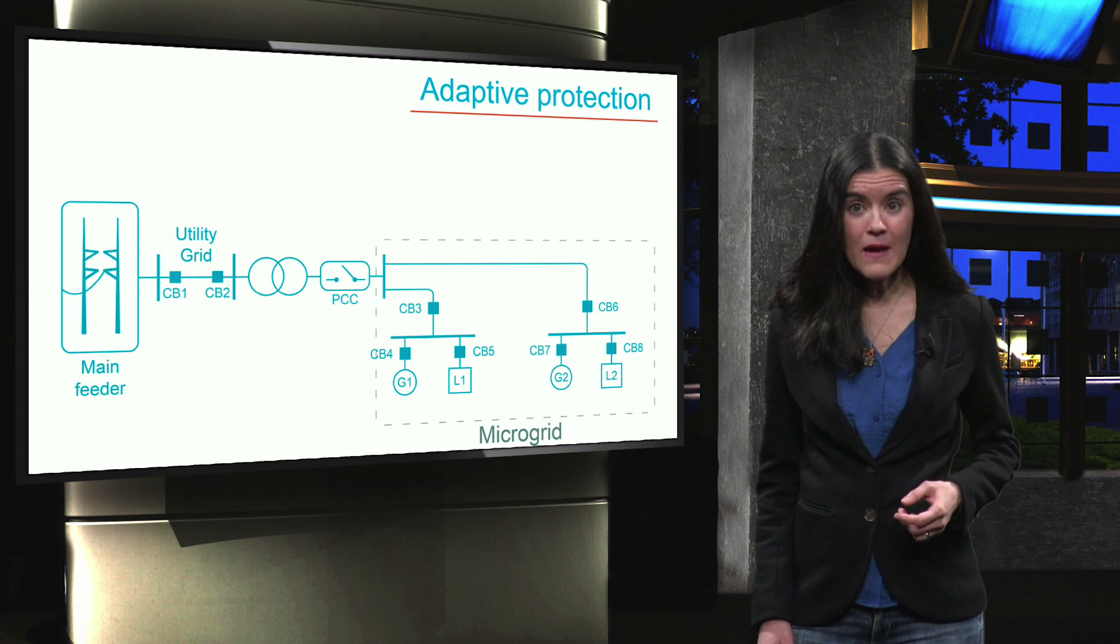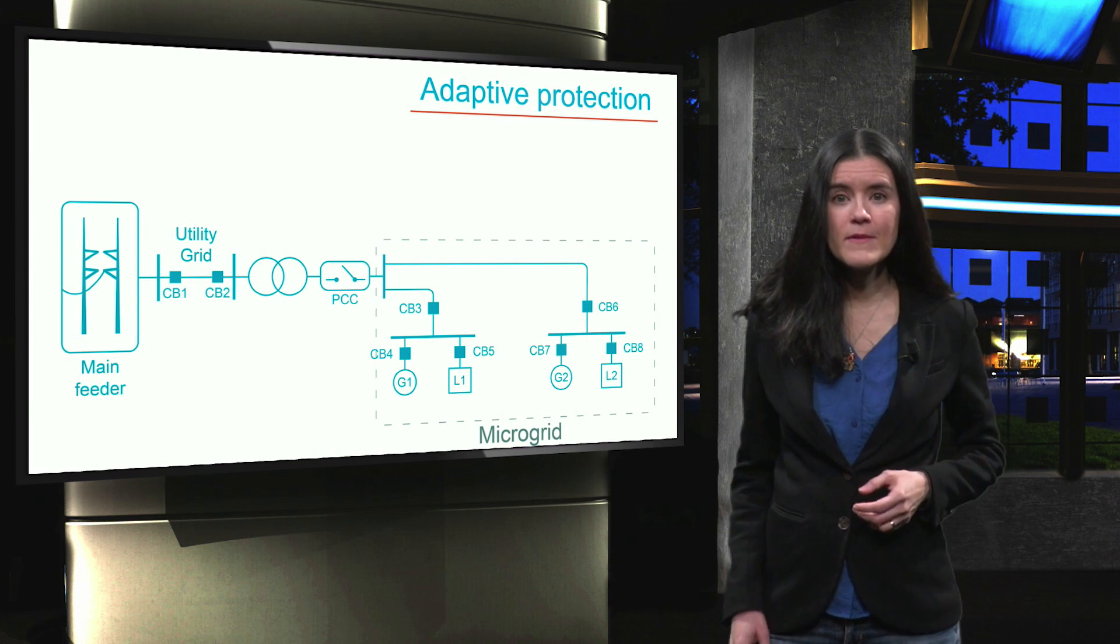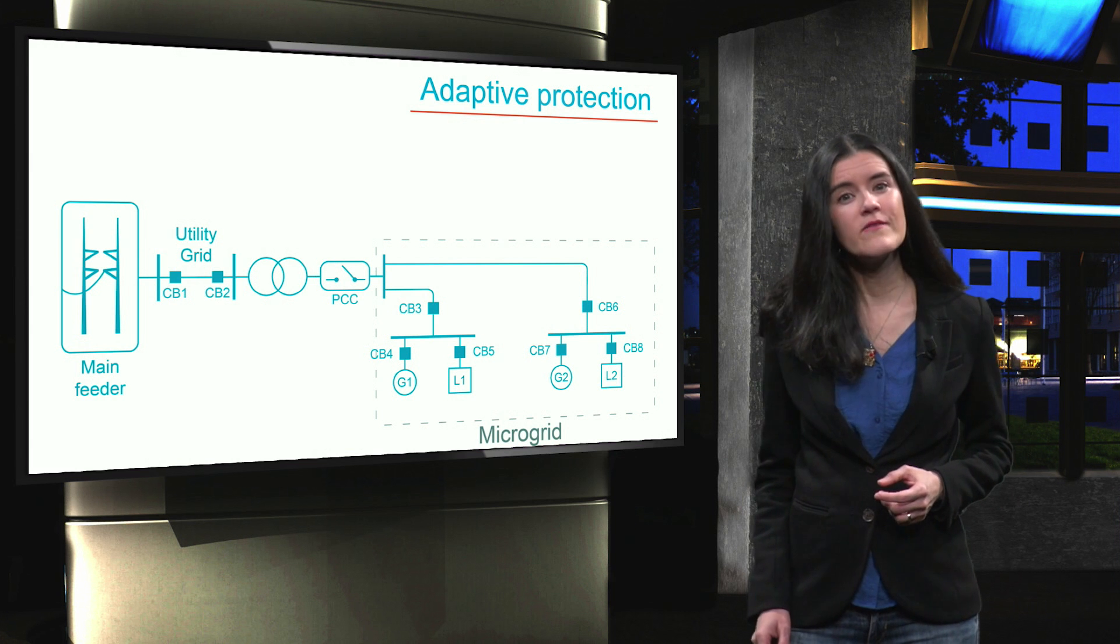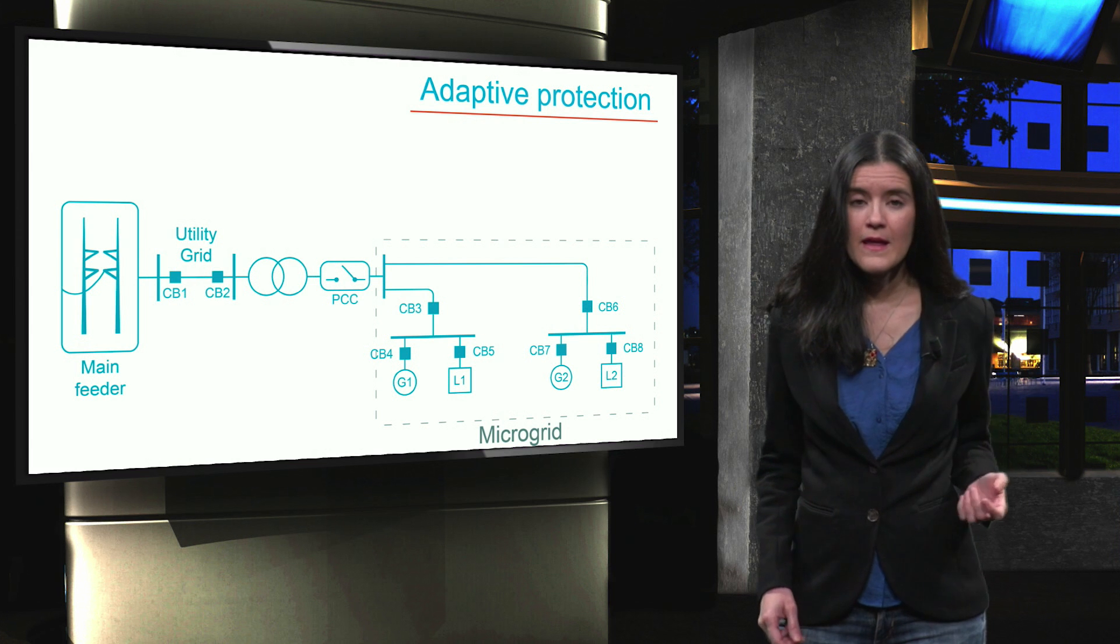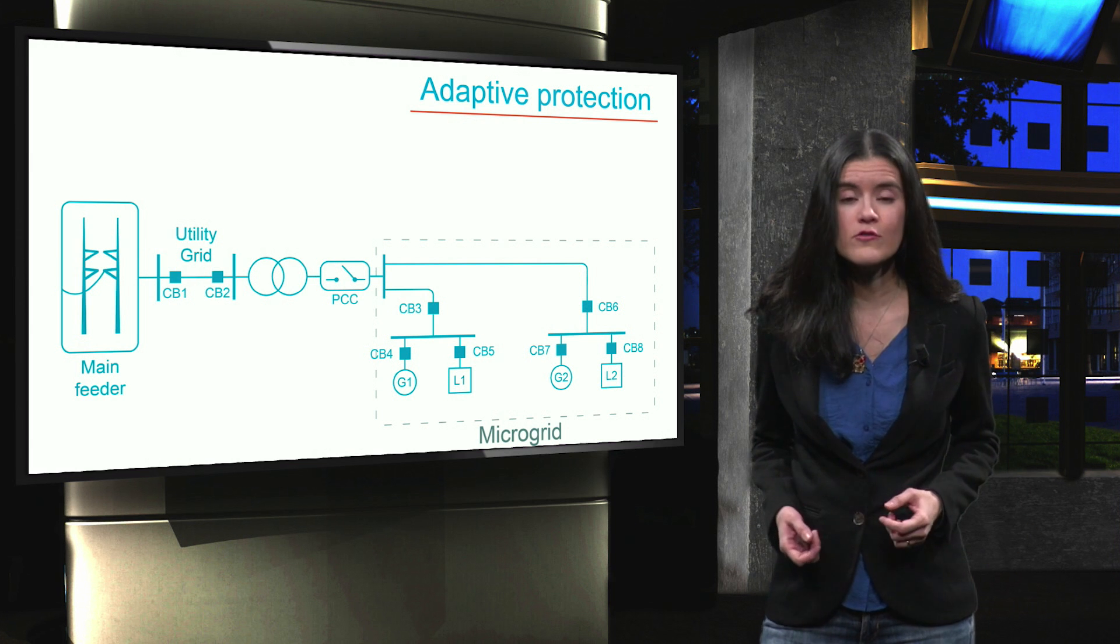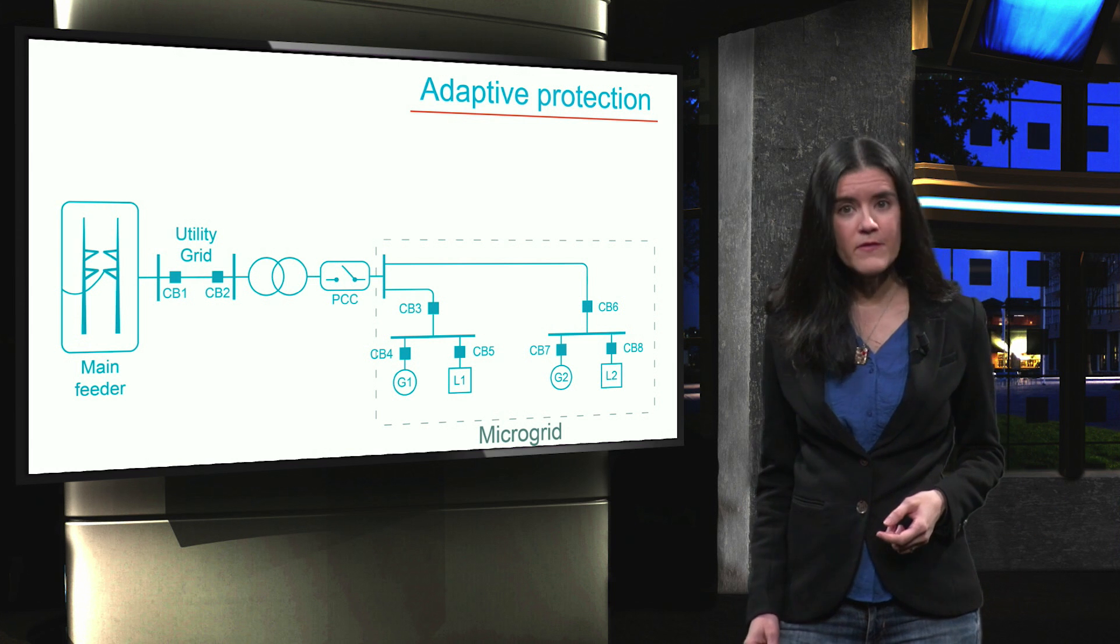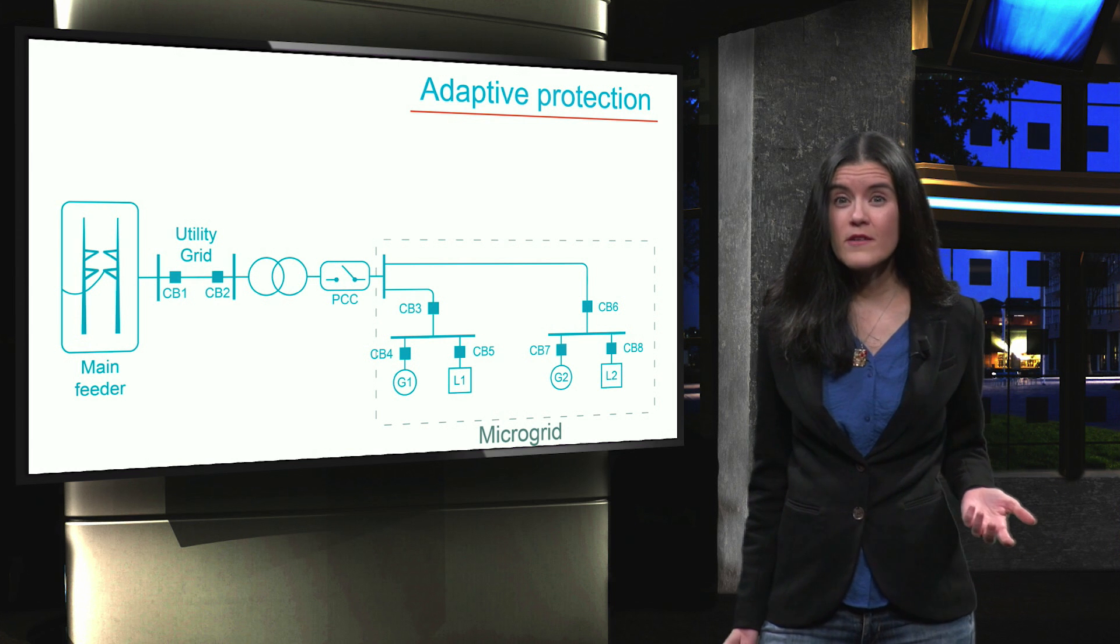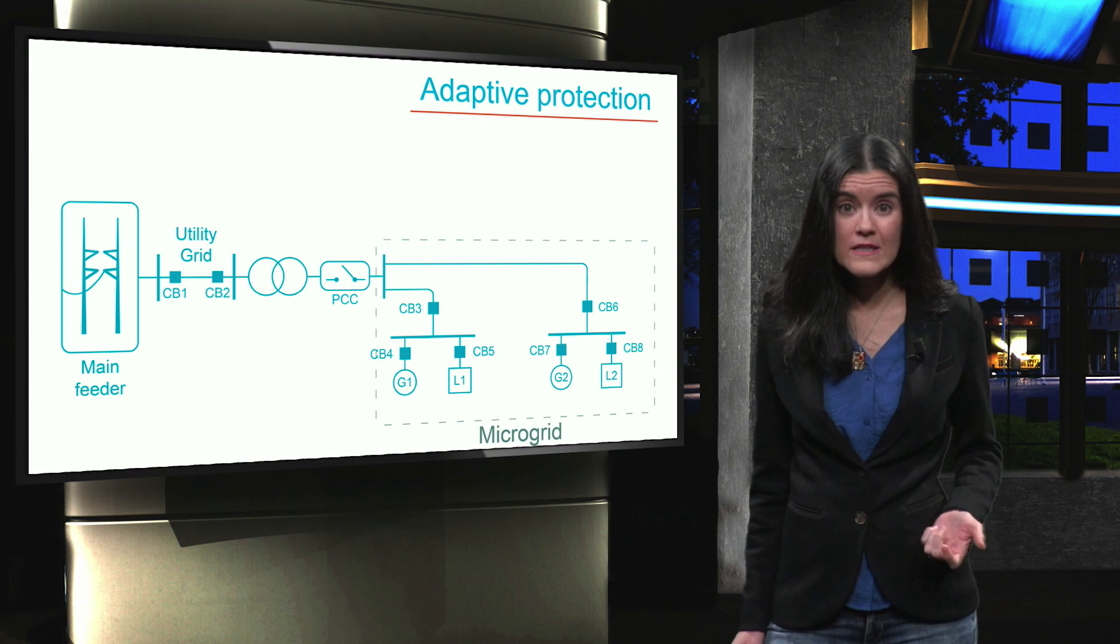Finally, we will discuss adaptive protection. Adaptive protection is a protection scheme that adjusts its protective response based on the network and system operating conditions. This selective response relies on the intervention of the microgrid's control system. To increase the reliability of the protection, adaptive schemes have been introduced such that the relay settings are adjusted based on their operation conditions.